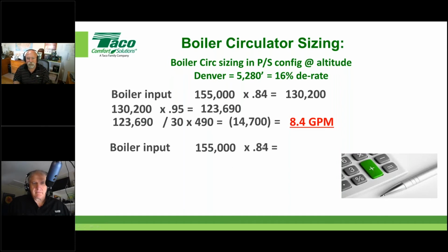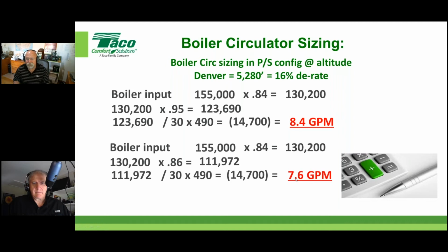Okay, here's the same derate, but at lower efficiencies. Lower efficiency, I'm going to slice that up even more. I'm going to be out here at a circulator at 7.6 gallons a minute. Remember, the boiler is 155. So this is where you want to have an understanding of why that boiler circulator sizing is important.